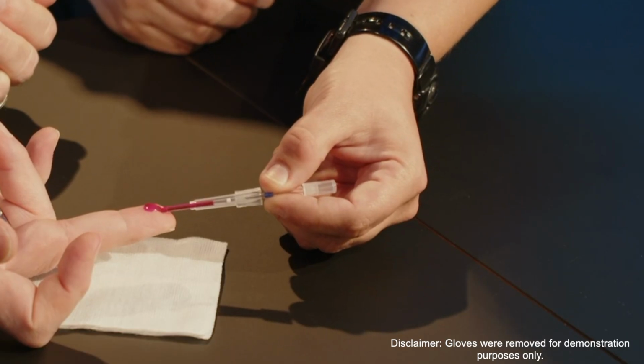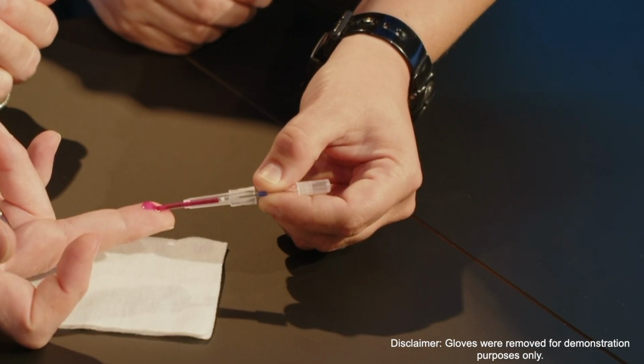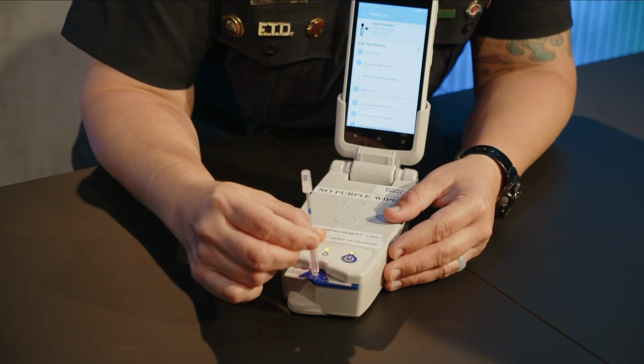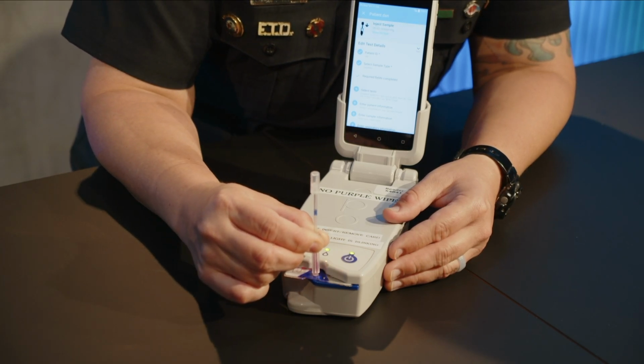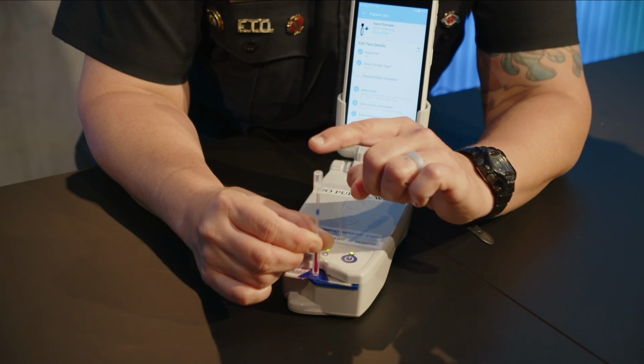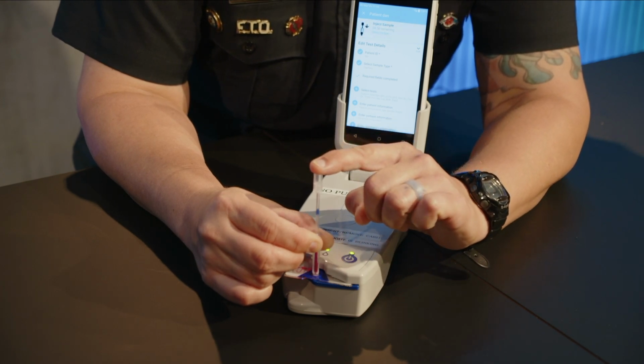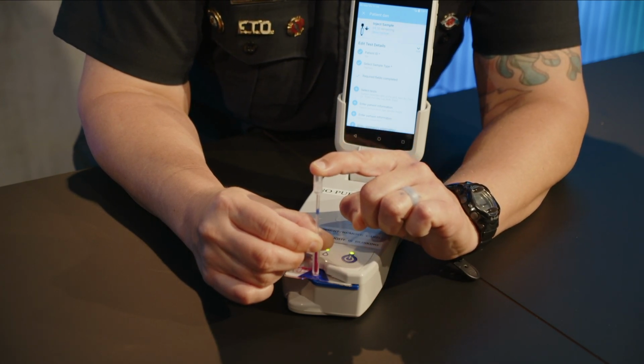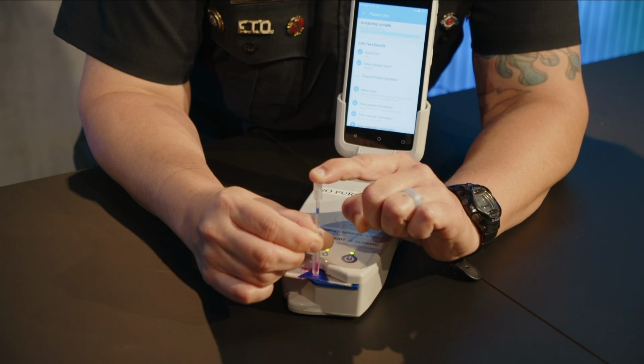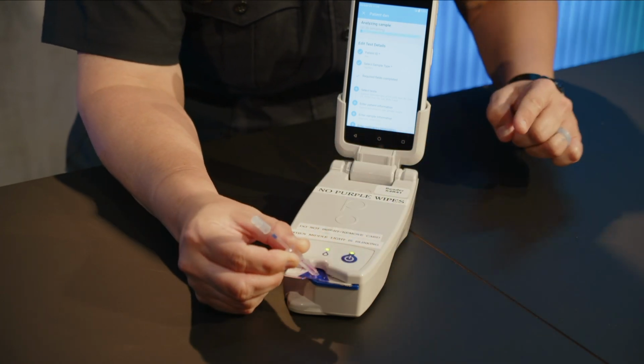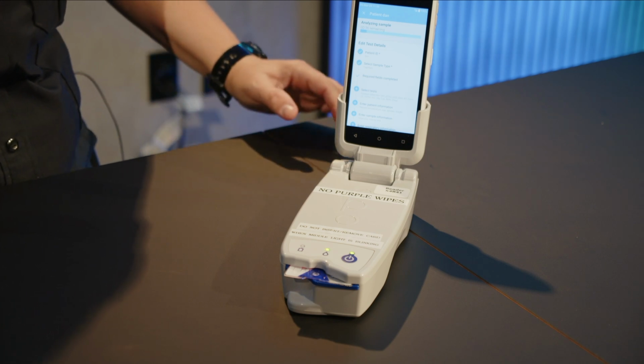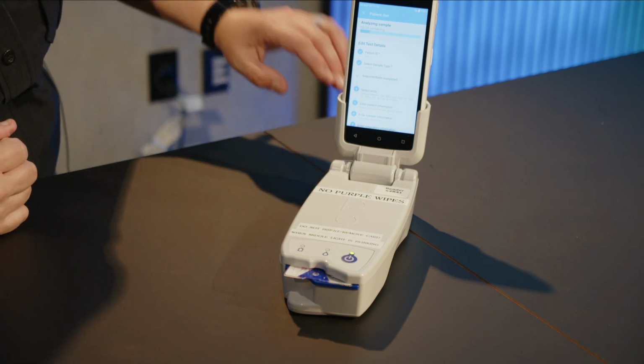Once the calibration is done, the system will prompt you to inject the sample. Attach the syringe to the test card's sample port. Give it a quarter turn to lock it in place, and then gently inject the blood. You'll hear a beep when the sample has been accepted. Don't keep pushing after that or you'll risk overfilling it. The system will then take about 30 seconds to analyze the sample.